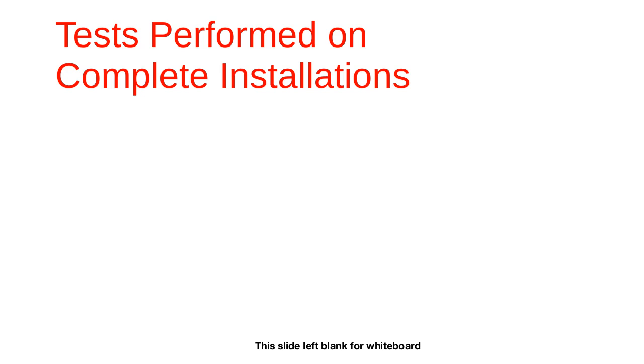We are told to describe the purpose of visual inspection as per the IEE standards, and it is that during visual inspection: number one, the equipment should comply with the product standard. Number two, the equipment should be correctly selected and erected. Number three, equipment is not damaged. That's another purpose of visual inspection.